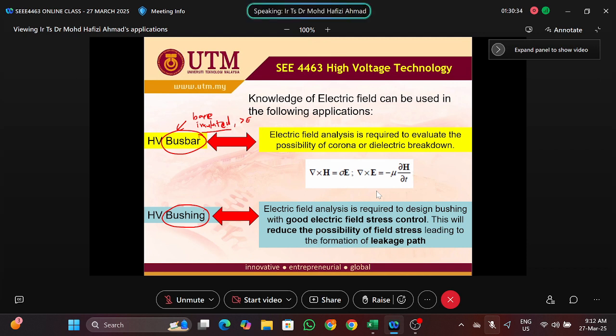This is because we have the insulator. If you go to somewhere like Petronas, they now use insulated bus bar more than bare bus bar, because the insulated bus bar provides more protection. In case something falls and touches the bus bar, there will not be any tripping on the relay or protection side, because the bus bar is already insulated.